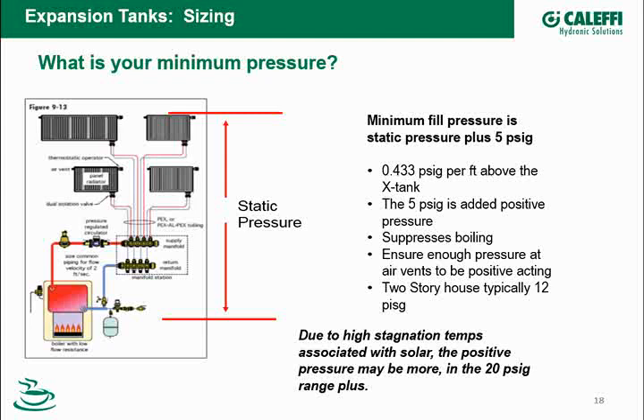In a typical two-story house, we're normally in the neighborhood of about 12 psi. That's why expansion tanks come pre-charged to 12 psi, and fill valve pressure is also set to 12 psi. That also means that if I'm going to do a heating system in a 3-story house, I'm probably going to have to increase the static pressure of my system, increase the pre-charge of my expansion tank, and increase the fill pressure on my fill valve.